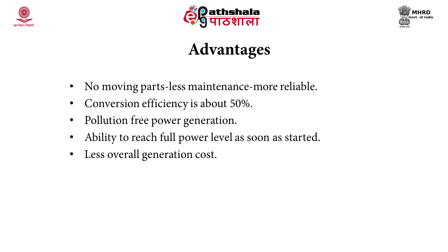The advantages of MHD generating systems: it has higher efficiency of 50–60% achievable by using a hybrid plant consisting of an MHD generating system and a thermal power plant. It has no moving parts. It can be started up quickly. Its output can be easily controlled by adjusting the strength of the magnetic field and the speed of ionized gas. It is a source of pollution-free power.